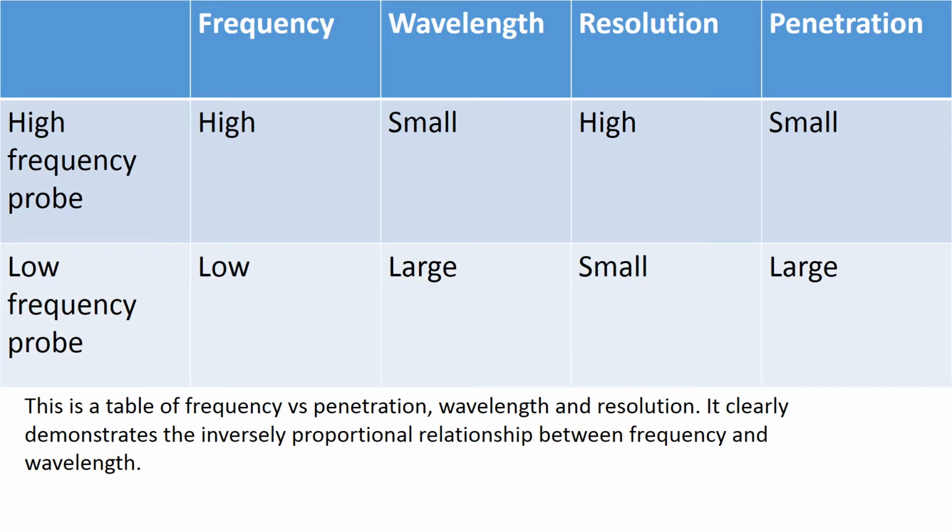This is a table of frequency versus penetration, wavelength, and resolution. It clearly demonstrates the inversely proportional relationship between frequency and wavelength. The high-frequency probe has a relatively small penetration but greater resolution, and the low-frequency probe has lots of penetration but little resolution.